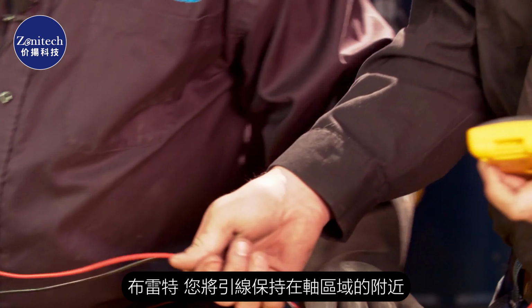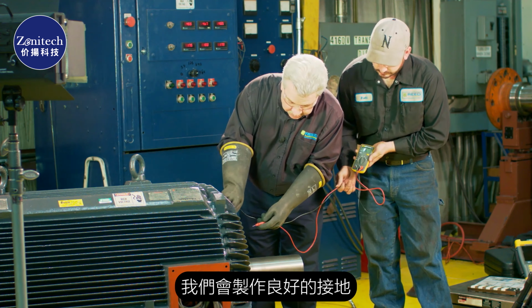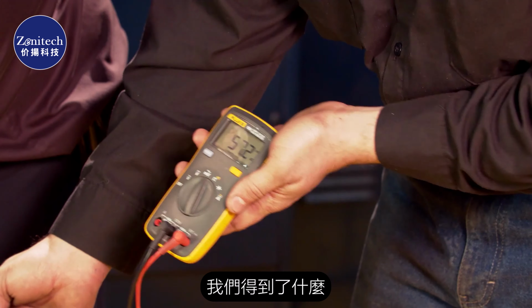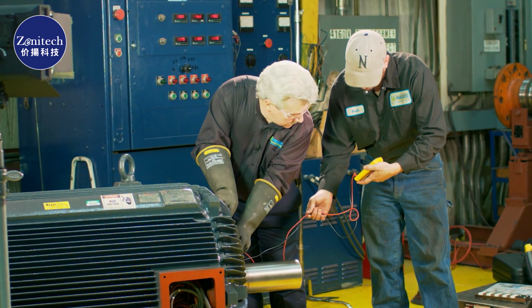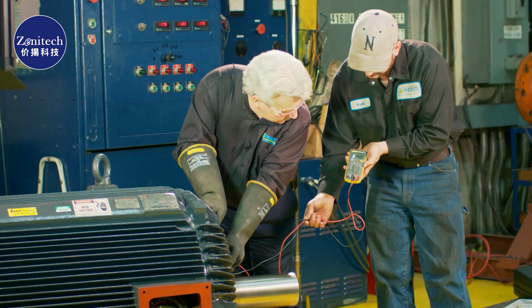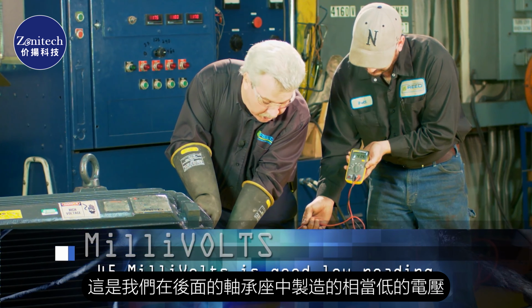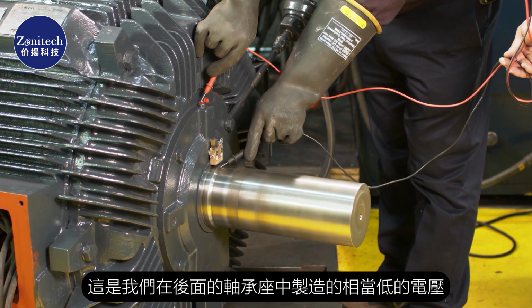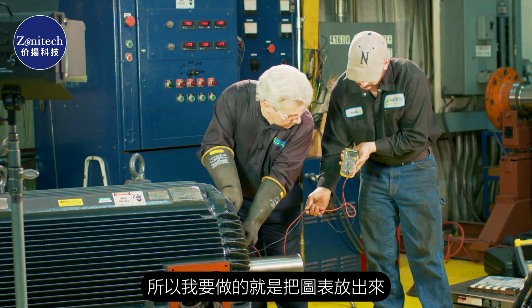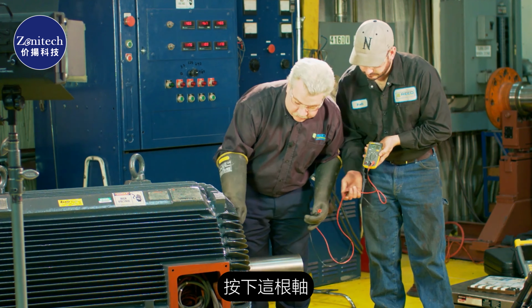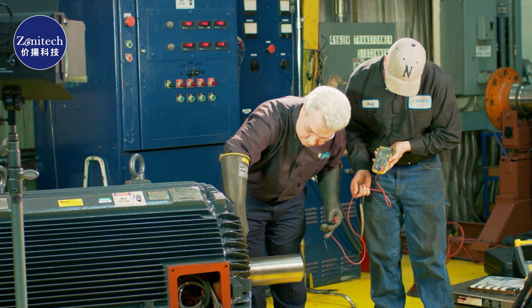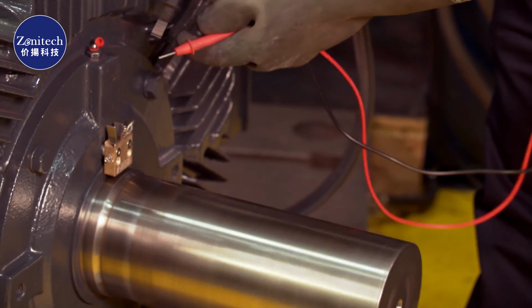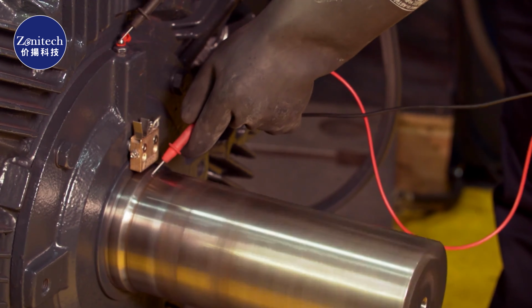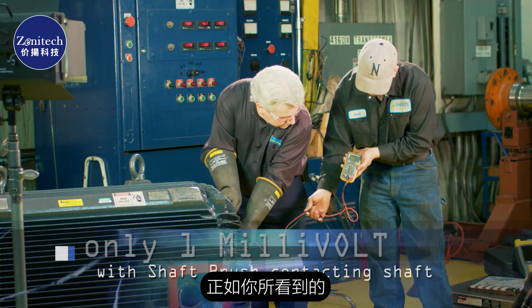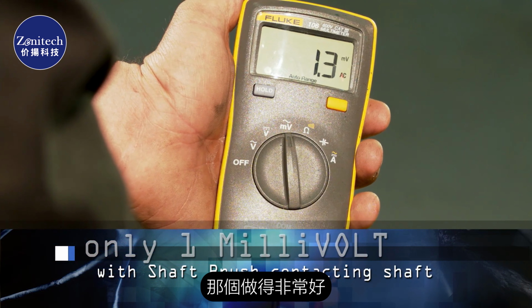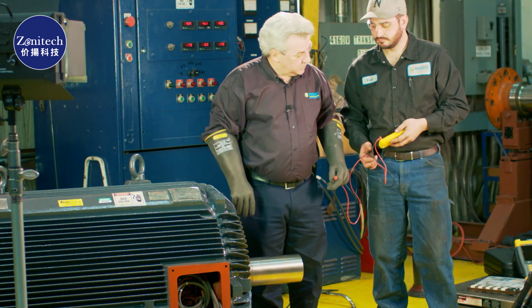Brett, you hold the leads up so she won't get up in the shaft area. We're gonna make a good ground. What do we got? Okay. Well, we're only reading about 45, which is pretty low. We've got an insulated bearing housing in the back end of this. But what I'm going to do is put the shaft thrust down. We're going to take another reading. As you can see, we got 1 millivolt. So that's pretty much it.